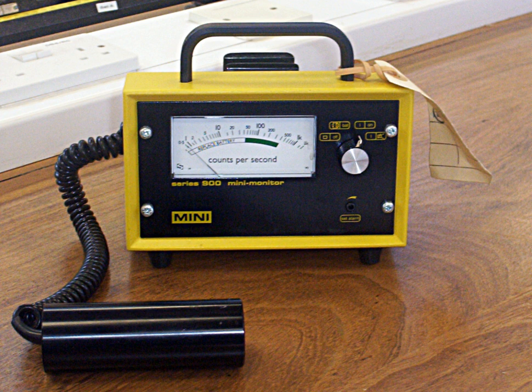More complex to achieve is a display of radiation dose rate, displayed in a unit such as the sievert, which is normally used for measuring gamma or X-ray dose rates. A Geiger-Müller tube can detect the presence of radiation but not its energy, which influences the radiation's ionizing effect. Consequently, instruments measuring dose rate require the use of an energy-compensated Geiger-Müller tube, so that the dose displayed relates to the counts detected.